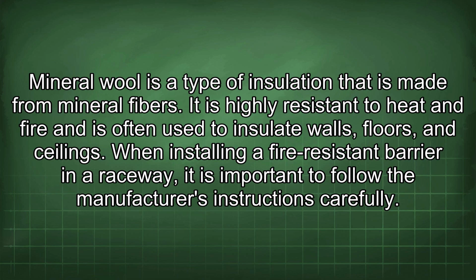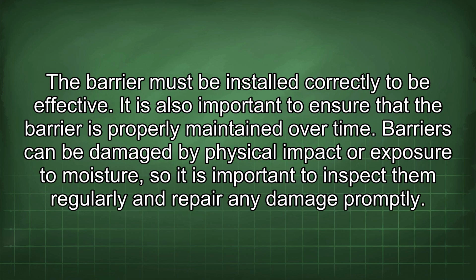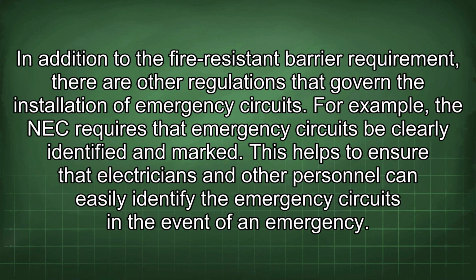When installing a fire-resistant barrier in a raceway, it is important to follow the manufacturer's instructions carefully. The barrier must be installed correctly to be effective. It is also important to ensure that the barrier is properly maintained over time. Barriers can be damaged by physical impact or exposure to moisture, so it is important to inspect them regularly and repair any damage promptly.